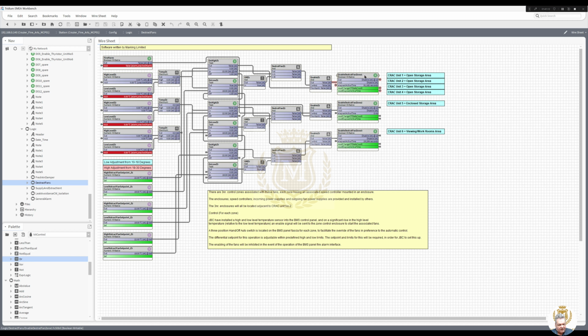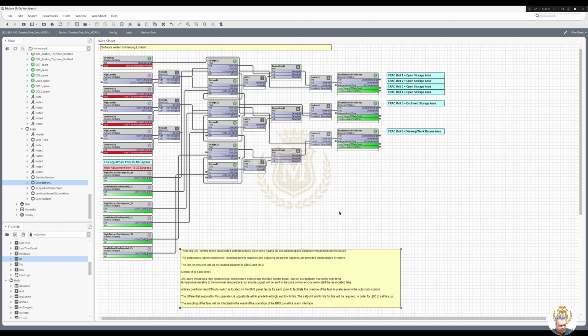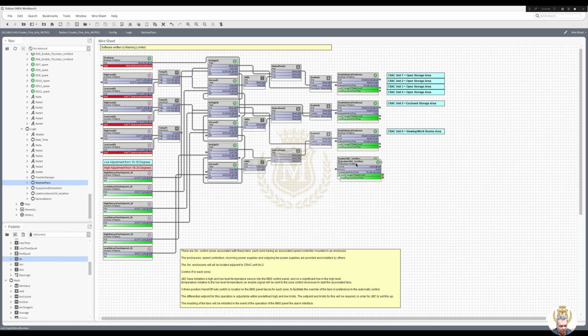So I know that once that's on, I want to enable 1, 2, 3 and 4. Once that's on, I want to enable 5. Once that's on, I want to enable 6. But what I'm going to do is put the enables again for the fans, for the CRAC units. So if I duplicate that, enable CRAC, yeah, I'll leave that as it is, CRAC unit number 1, duplicate that, number 2.